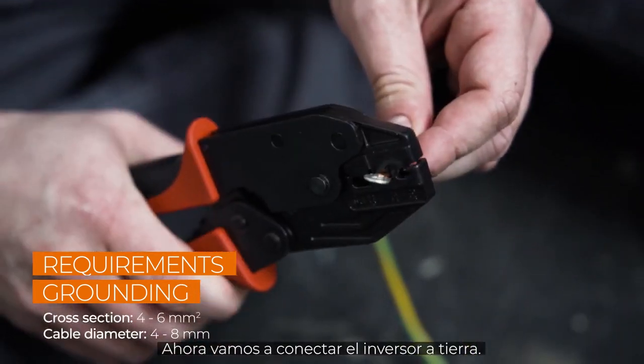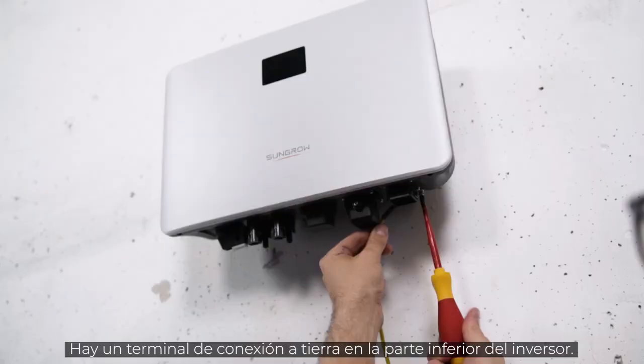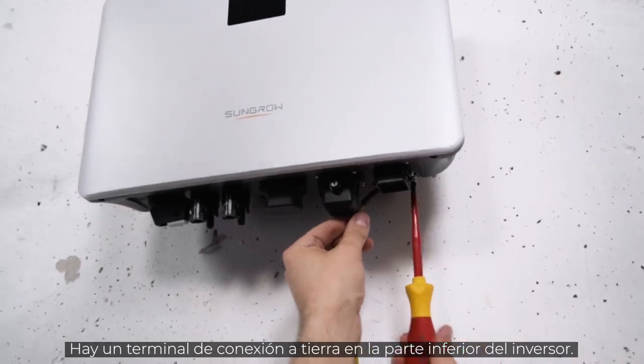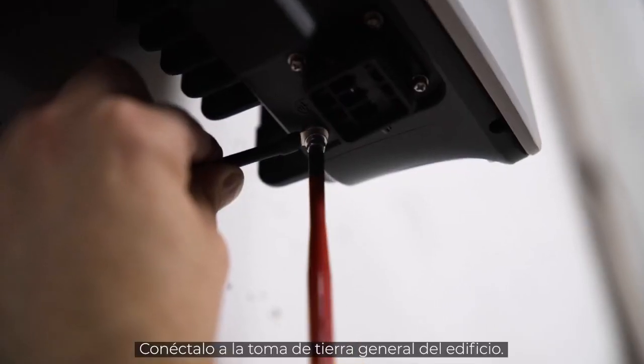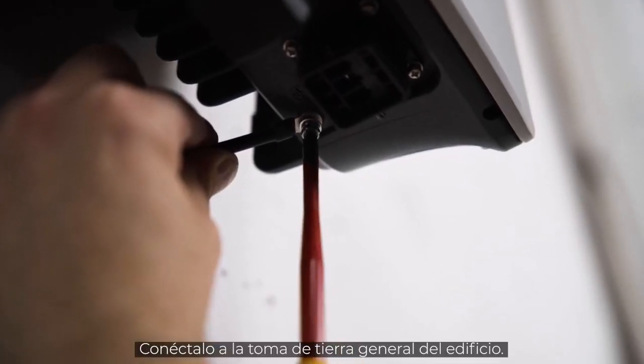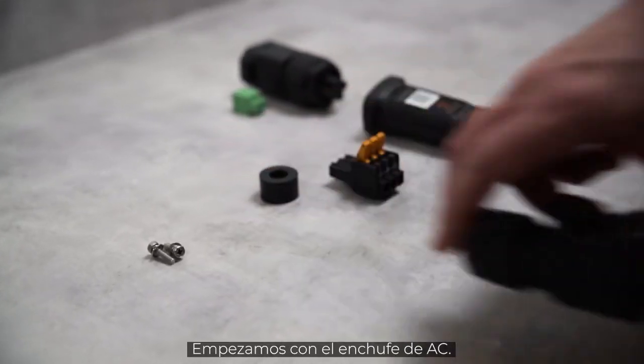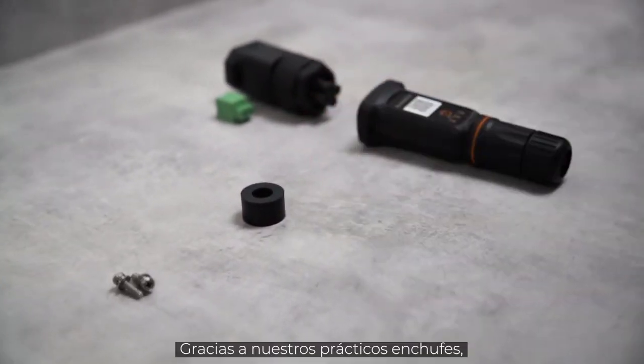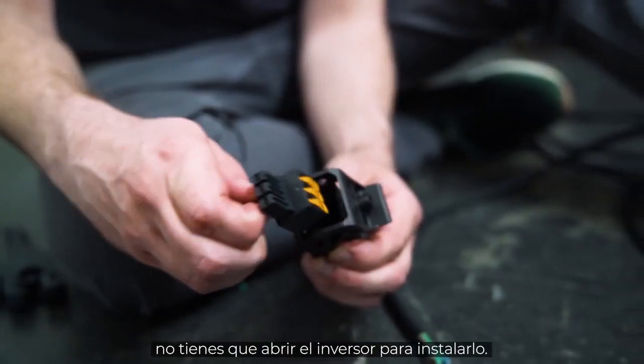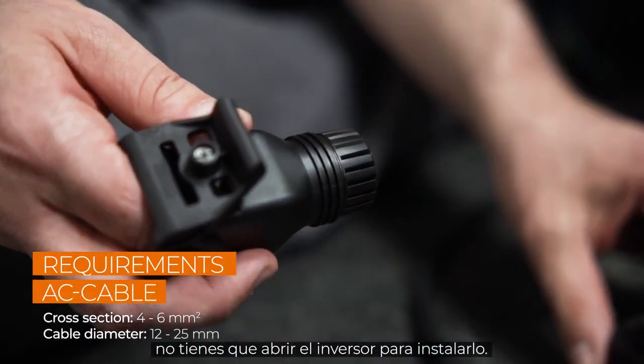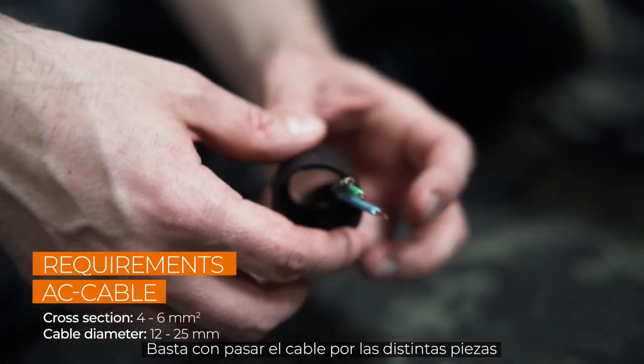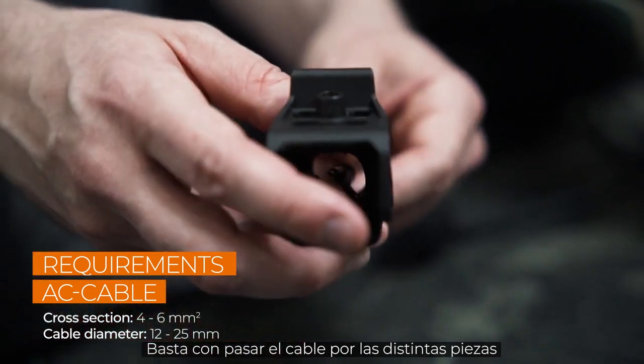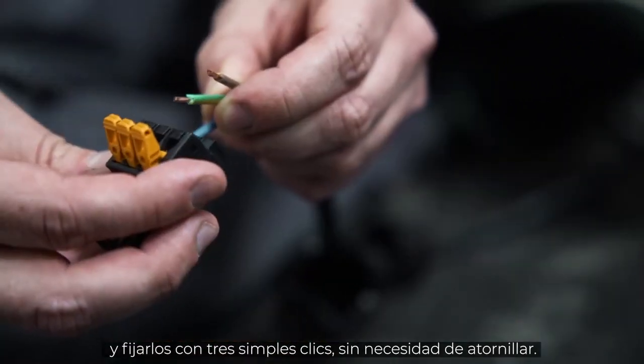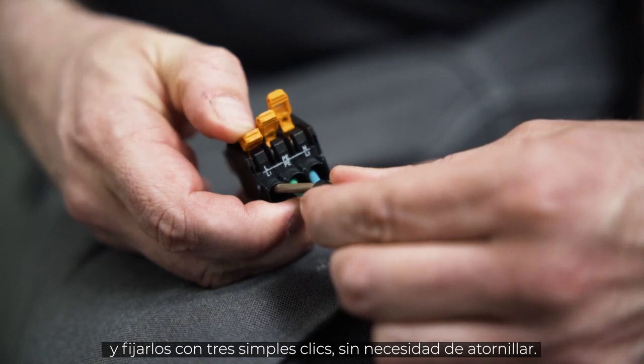Now let's connect the inverter to ground. There is a grounding terminal at the bottom of the inverter. Connect it to the general grounding of the house. We start with the AC plug. Because of our handy plugs, you don't have to open the inverter for installation. Simply pull the cable through the individual components and fix them with 3 simple clicks, completely screw-free.